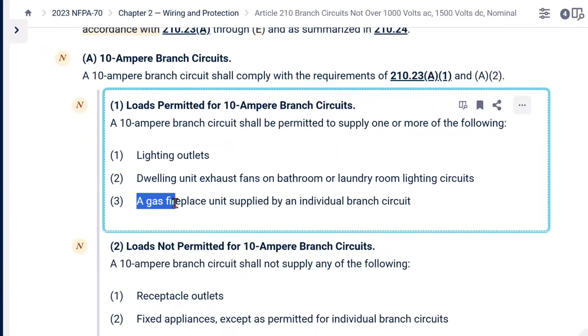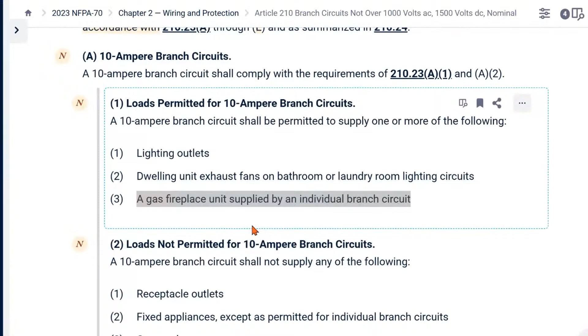But here it says gas fireplace units supplied by an individual branch circuit. Now, here's the problem with those. The reason they're going to get rid of this, okay, is because typically these are cord and plug. And so you have a prohibitive requirement for these 10 amp branch circuits, right? And the prohibitive requirement, even in the 2023 code, is right here. You can't supply receptacle outlets, okay? There's a couple things that you can't supply, obviously, with the 10 amp branch circuit. But this typically comes from the manufacturers, and it might have a connected cord and plug. Well, that would mean that there has to be some type of receptacle application to that, right?